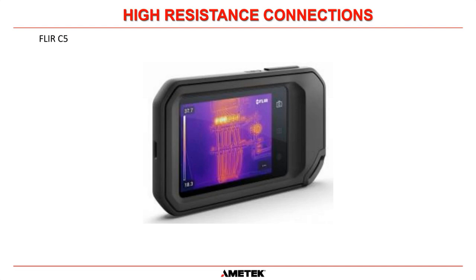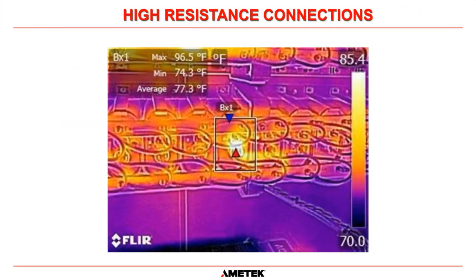And the best way to check for these things, rather than go in and check every connection with a torque wrench, is to use thermal imaging, infrared thermal imaging. And I've put a picture here of the FLIR C5 camera. That's what most of our technicians in the field use. We are moving on to the FLIR Edge now. We are phasing these out and moving to the FLIR Edge. But they're very, very good.